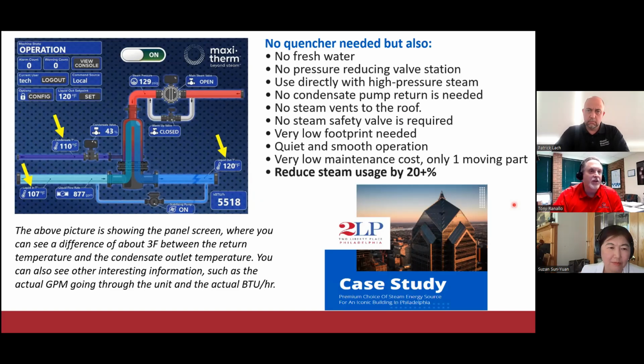desirable operation. They didn't have to have a quencher. We'll talk about the low temperature condensate that they have to emit to drain. There's no fresh water makeup, obviously, when we do that. There's no pressure reducing valve stations. We're using the high pressure steam directly. They did not need a condensate pump return because we're just wasting the condensate to drain. No steam vents to the roof, and no safety relief valve is required, because if the boilers providing the steam were valved at safety valves at 300 PSI, we would just stamp our skid for 300 PSI.